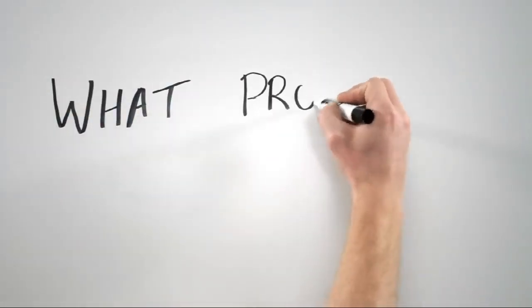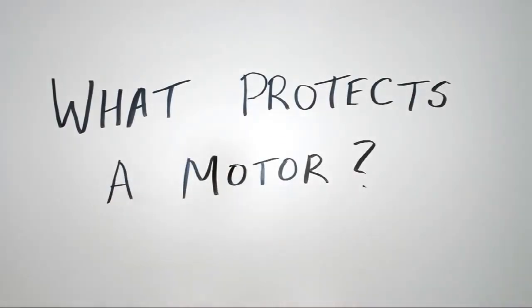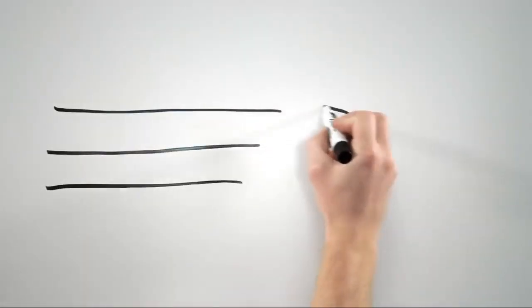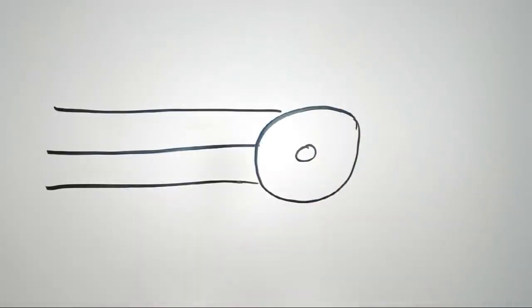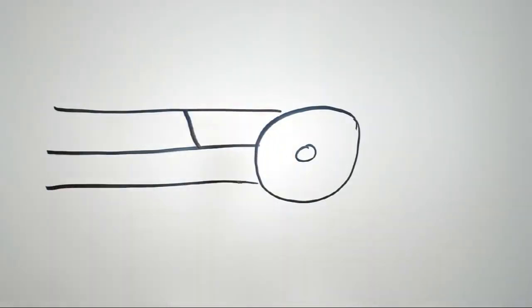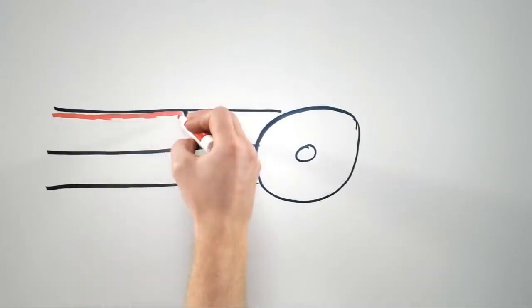Now that we understand how to turn on and off a motor, how do we protect it? Let's briefly talk about short circuits. Well, what can cause a short circuit? When we're talking about motors, one of the ways we can see a short circuit is when we get a phase-to-phase short. So let's say a forklift operator accidentally nicks the wires going to a motor. He doesn't cut all the way through the wire, but enough to cause two of the phases to touch each other.